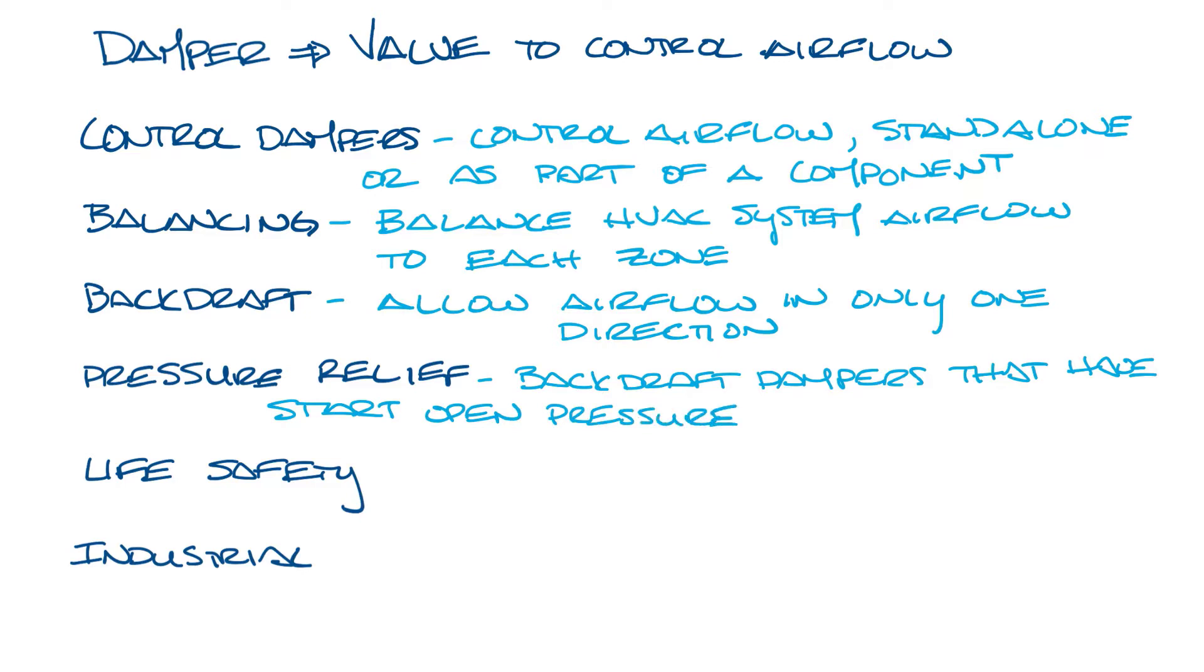Life safety dampers are put in openings in walls, ceilings, and floors to prevent the spread of smoke and fire. They operate automatically when they detect smoke or fire. In the case of smoke, they are designed to close quickly to restrict the spread of smoke in an HVAC system, but less often they can be designed to open to control the movement of smoke within a building.